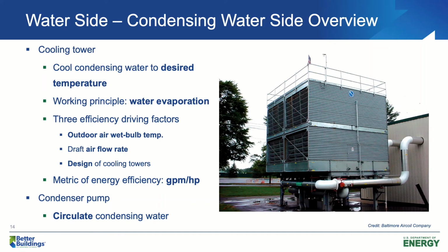Cooling towers. The job of cooling towers is to cool the condensing water so we can reject heat from chillers. The working principle is very simple. It works by evaporating water. Since we are losing water all the time, we need to regularly add makeup water to our cooling towers.